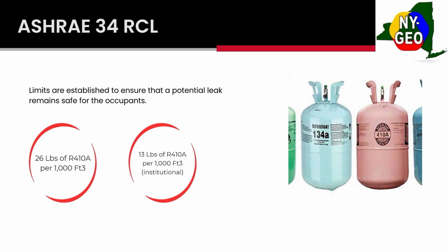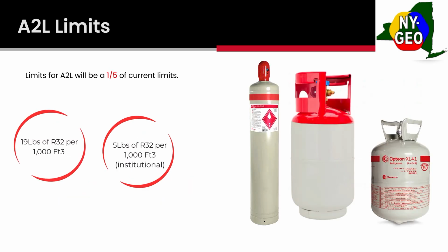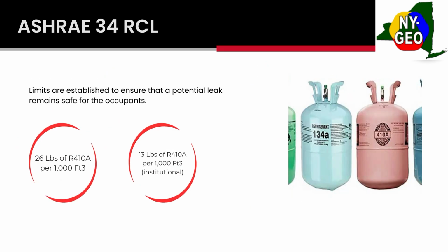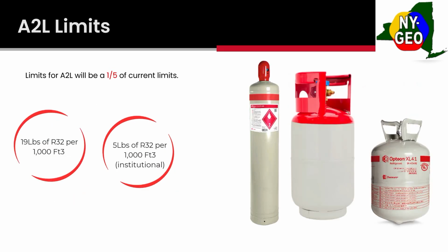Now, when we look at A2L, they're not using RCL. They're using the LFL, the lower flammability limit. And you can see your releasable charge is about 1/5 of 410A. So we're talking 19 pounds of R32 in a 1,000 cubic foot area, or 5 pounds in institutional. You go back, there we go, 26 pounds. So that is a huge difference right there. And that's why we're here to talk about design considerations and how we're going to work around those limitations.